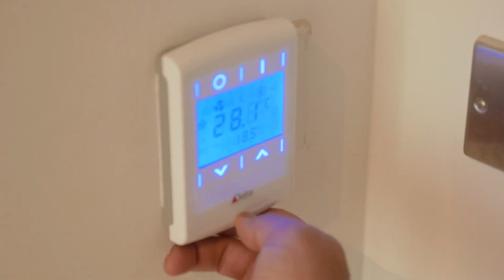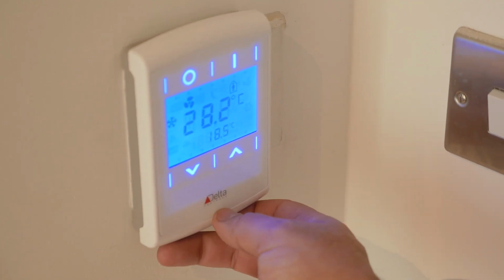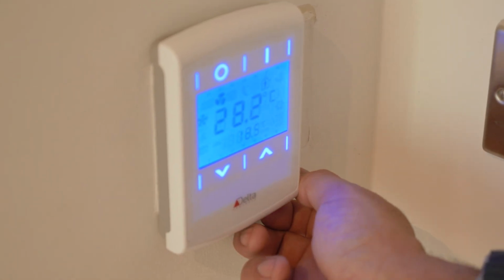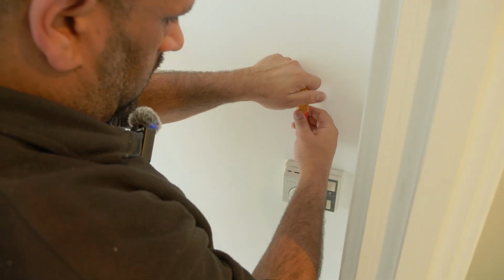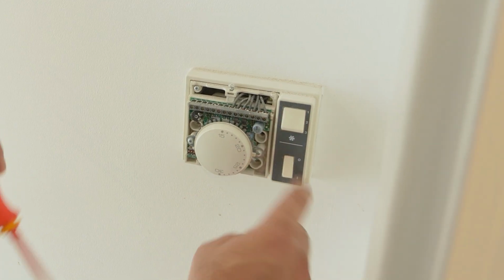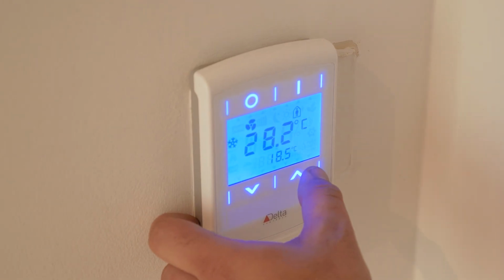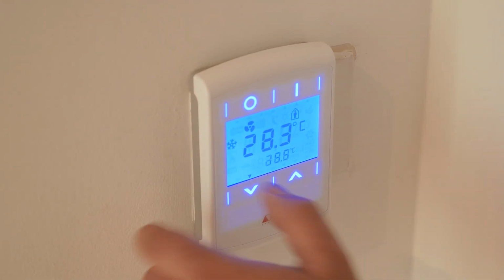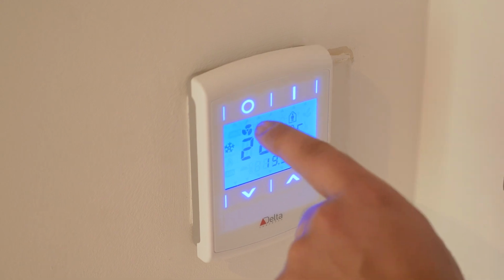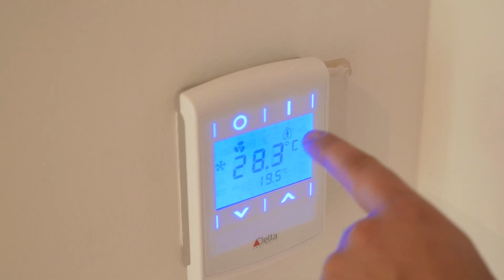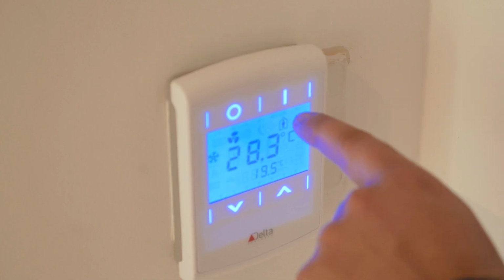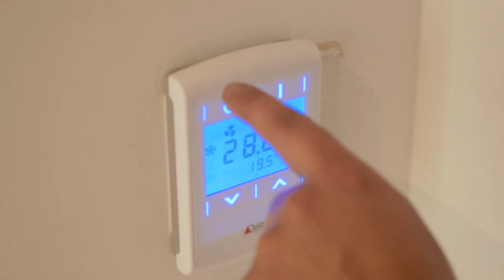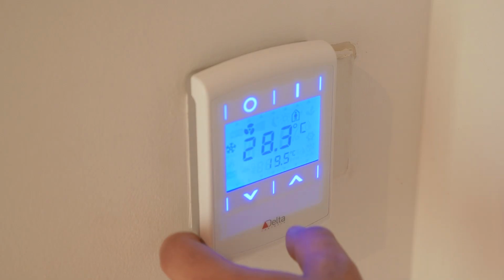This is the most important bit that you homeowners and the end user will obviously interact with. This is the wall thermostat controller that we installed. We replaced the old Honeywell Star controller that was here. The older Star controllers actually had the fan coil unit control section in here with fan speeds on, off, and all the other things. This is an up-to-date LCD model and it integrates with the Delta fan coil unit controller. So you have a full range of temperature. At the bottom, you have the current temperature that's in the room. It auto adjusts the fan speed according to the load. It lets you know if there's occupants, we're measuring temperature within the space. And on the left-hand side, it's in cooling mode. It'll give you the mode at which the fan coil unit is in currently. On and off, very easy to use and very user-friendly.